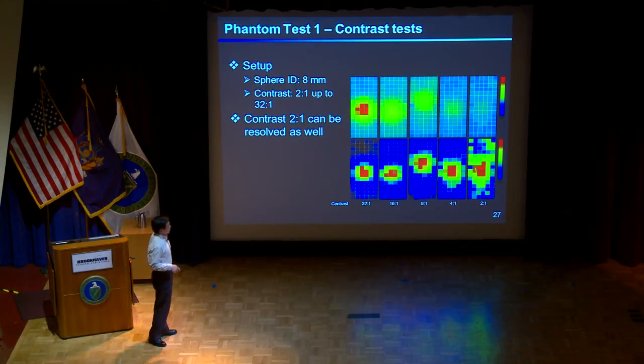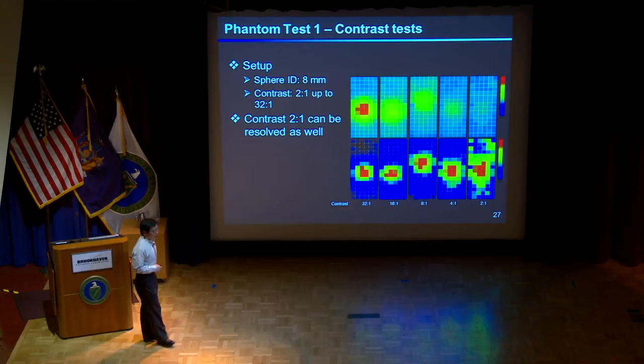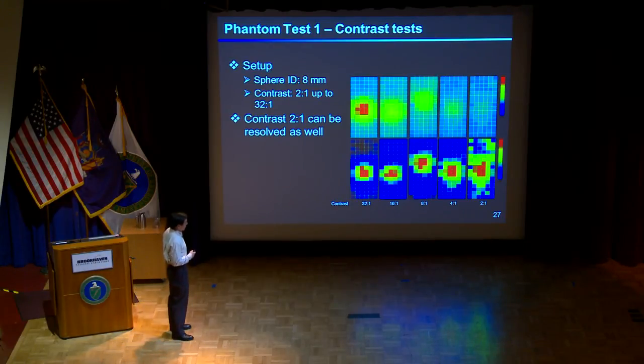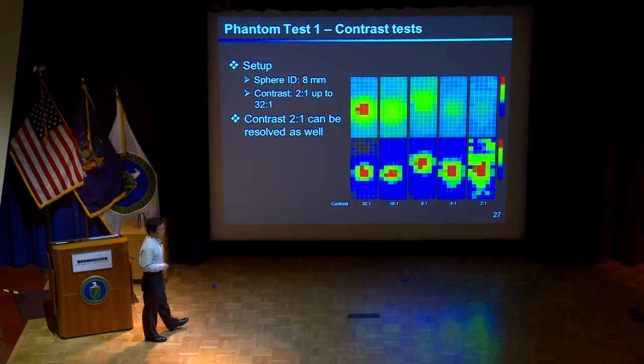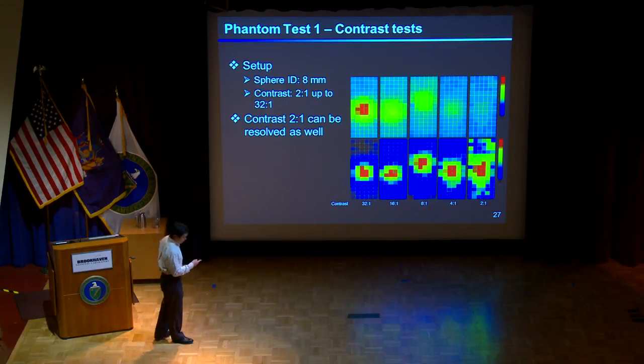But even in this case, our camera can still see small tumors such as 8 millimeter. Well, 8 millimeter is not the smallest one we can see. The reason is, when we did this test, we didn't find a smaller, like 5 millimeter sphere. That's the one we want to test because our detector is designed with an intrinsic spatial resolution of 5 millimeter.